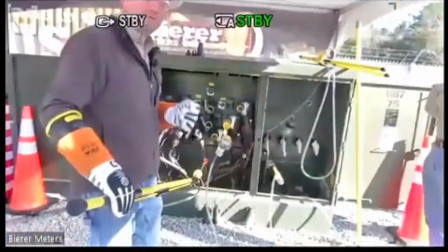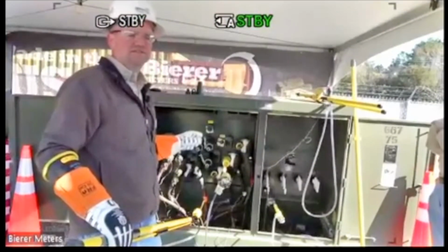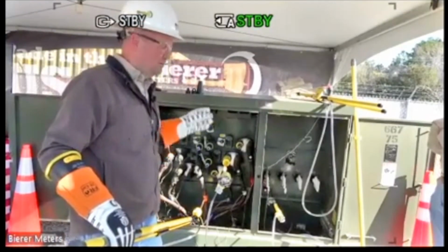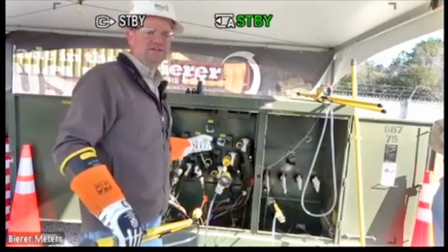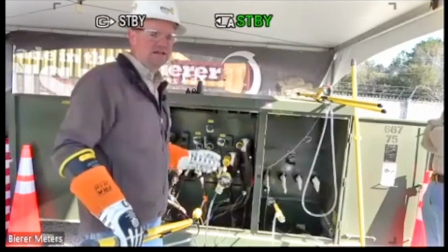But remember what I mentioned earlier. I'm actually testing the high pot doing this. So I can verify that the high pot is a good accessory, a good adapter before I go using it. Okay. But that's what you would see on a bolted fault, is that number right there. That's what you should expect to see.